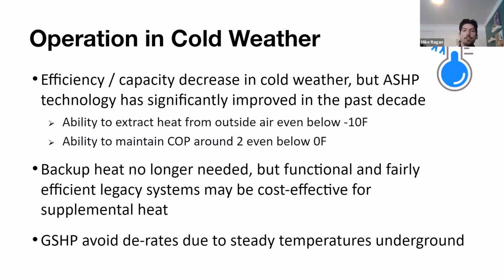So when we're talking about how systems operate in cold weather, fortunately over time, the skepticism has gone down quite a bit. But when I first entered the heat pump industry about 6 years ago, there was absolutely still a lingering sentiment that heat pumps could not possibly heat in the New England climate. And this was certainly a mindset that stayed over from previous generations of heat pump equipment that didn't have the robust technology necessary to extract heat at those colder temperatures. But with that said, we have had various advancements in heat pump technology over the past decade, to the point now where all manufacturers effectively have their cold climate model series for their heat pump equipment.